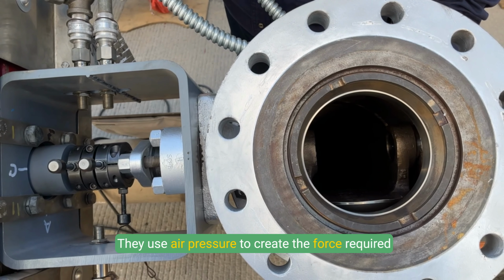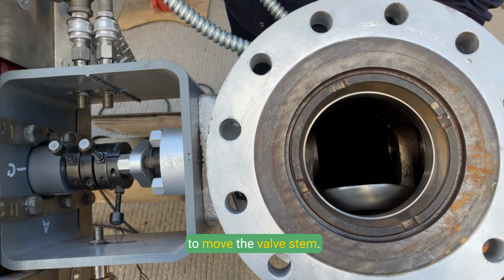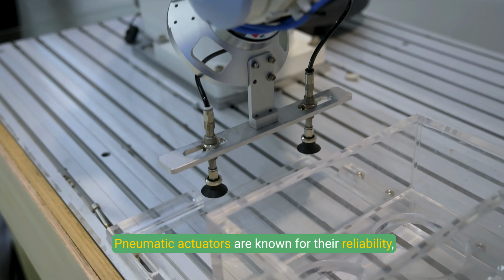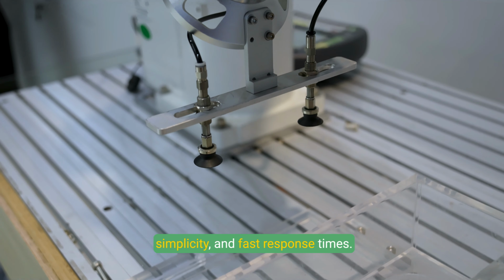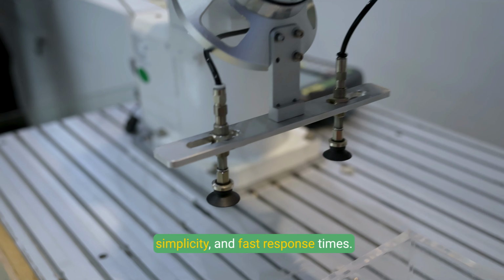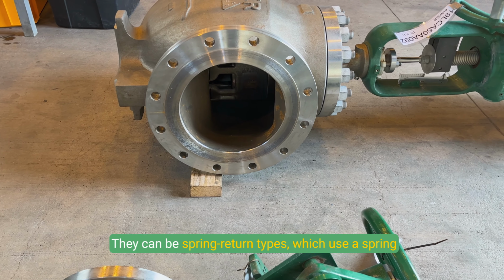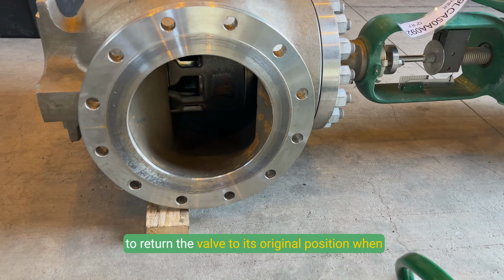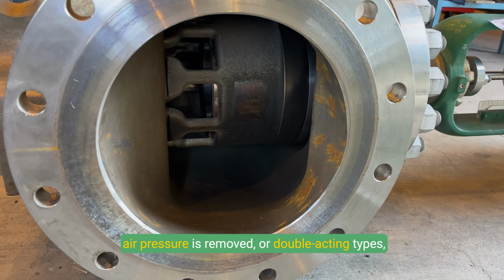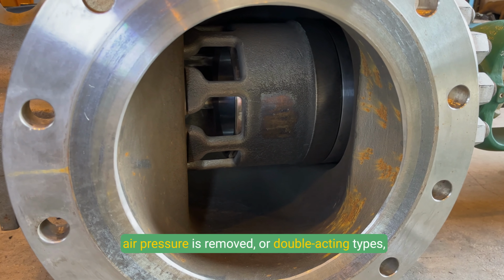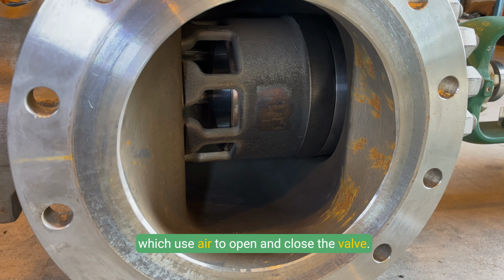They use air pressure to create the force required to move the valve stem. Pneumatic actuators are known for their reliability, simplicity, and fast response times. They can be spring return types, which use a spring to return the valve to its original position when air pressure is removed, or double-acting types, which use air to open and close the valve.